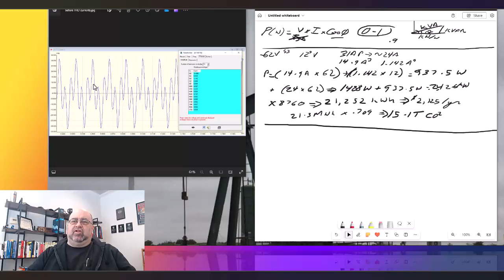Now, let's see what happens when we apply the corrections. So this is at 180 hertz, looks real ugly. We put the ground filter in place. This is now 60 hertz. Yeah, quite dramatic, isn't it? So this now is the fundamental at 60 hertz. This here is now our third harmonic, and then our ninth harmonic, there's a little fifth and seventh, but we're more worried about our ninth harmonic. So let's go ahead and see where we are.